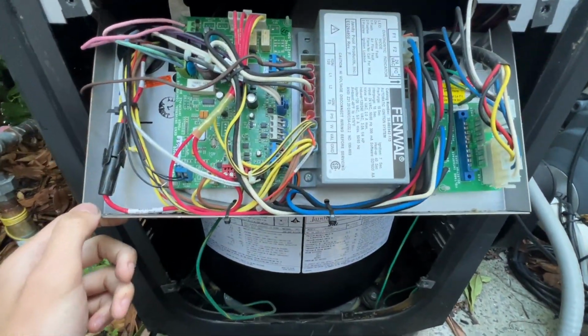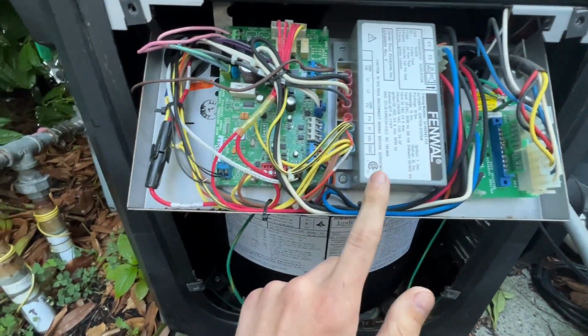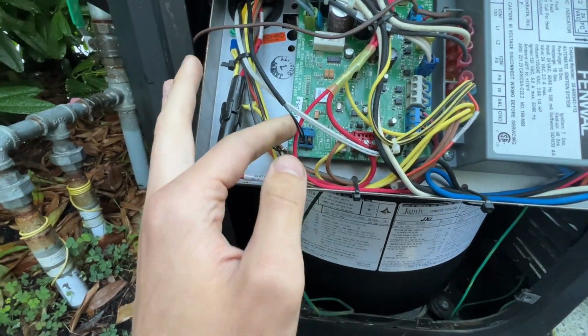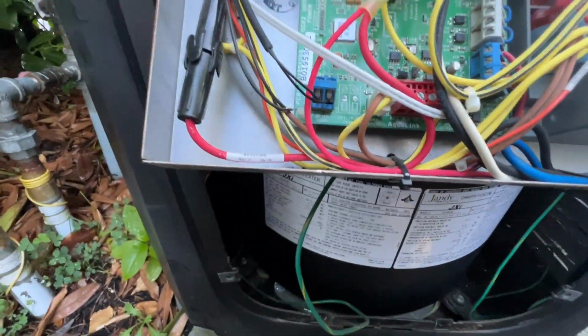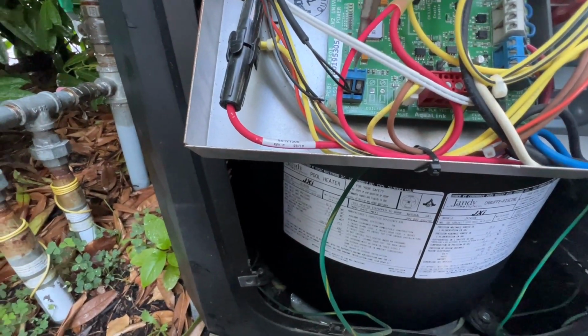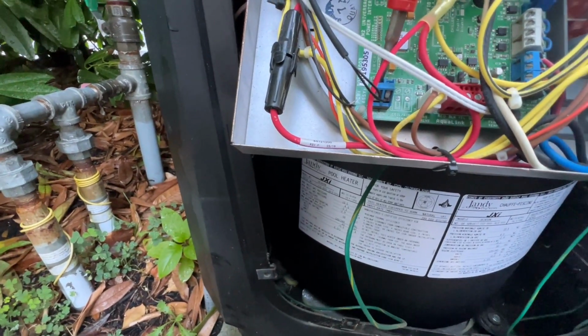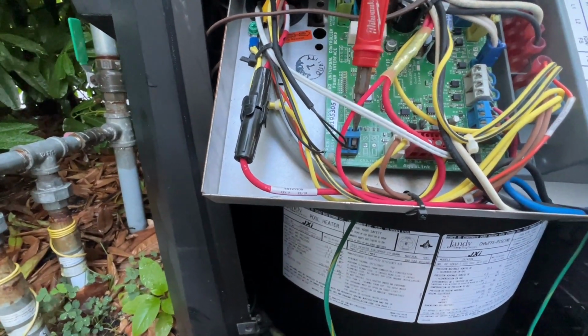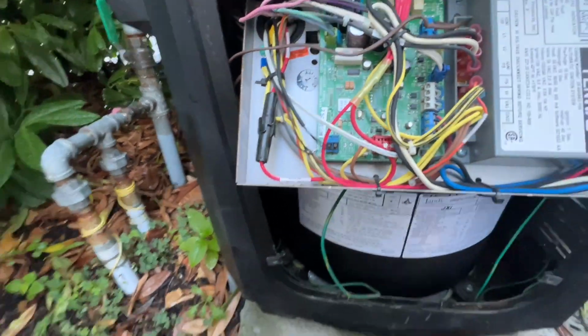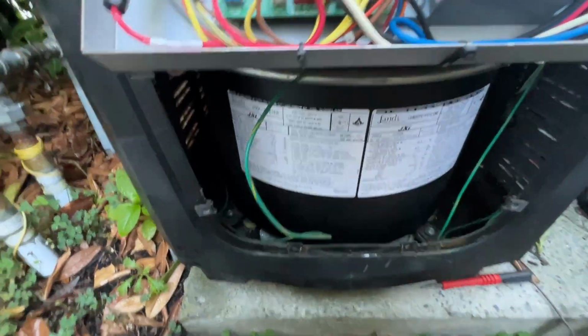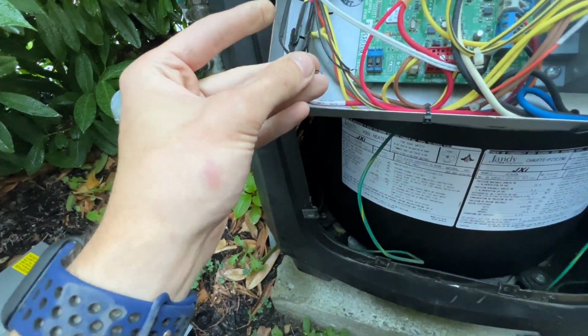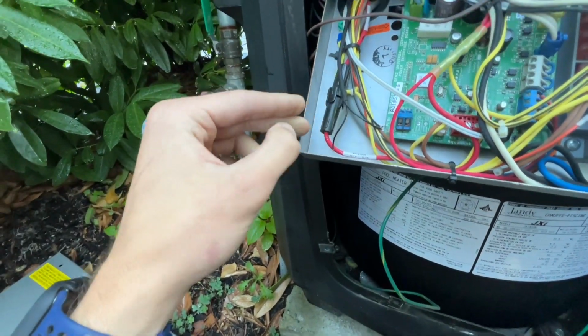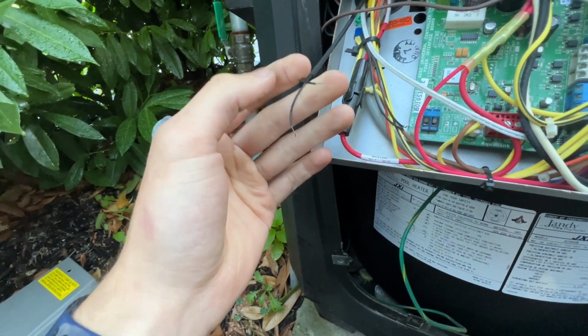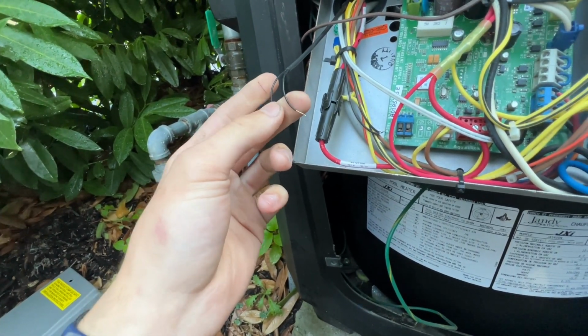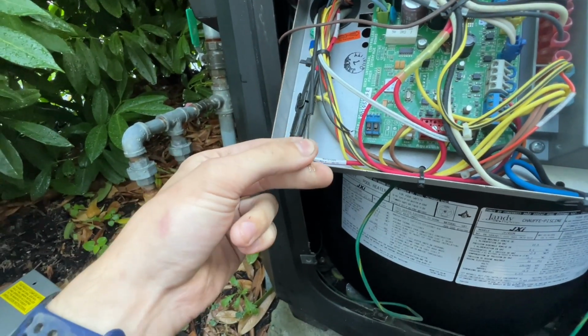This is our control board, our ignition board, and right here, these two black leads are our water temperature sensor. First thing I'm going to do is loosen that up. I've got my little Milwaukee pen screwdriver, and I'm going to test the resistance across the temperature sensor, because at whatever temperature it is, it should be reading a specific resistance value, which I have a chart for on my phone.